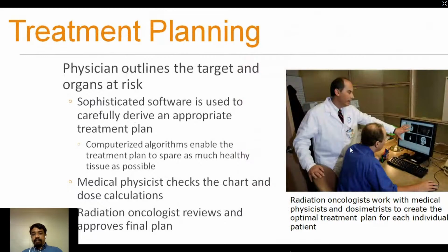So treatment planning is a very important concept. What we do is we do a CT scan and we import the entire CT scan, and the radiation oncologists outline the area of interest where they want to give radiation. We as physicists do the plan, and this plan will be transferred by computer to the treatment machine. The treatment planning system has a modeled beam, how the beam output of the machine has been modeled, and using a Monte Carlo simulation, we can simulate how the doses will be on the patient.